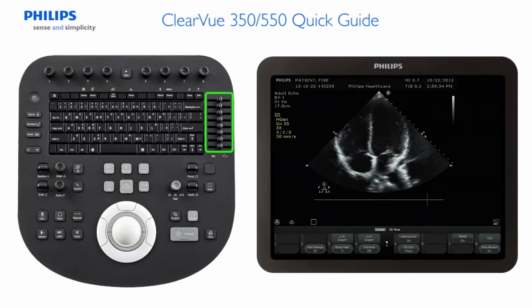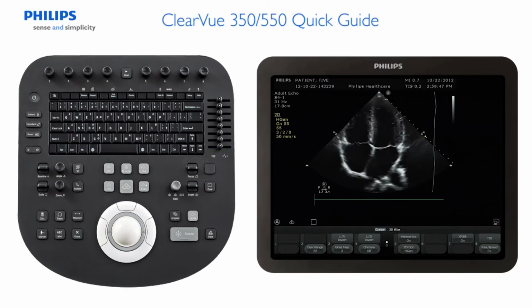To the right of the keyboard are the time gain compensation slide controls. These horizontal slide controls adjust amplification of the returning signals at a specific imaging depth. Lateral gain controls are available on the sector array transducers.